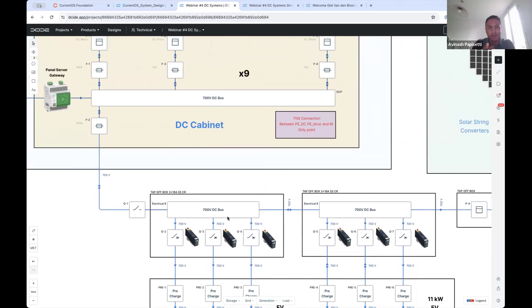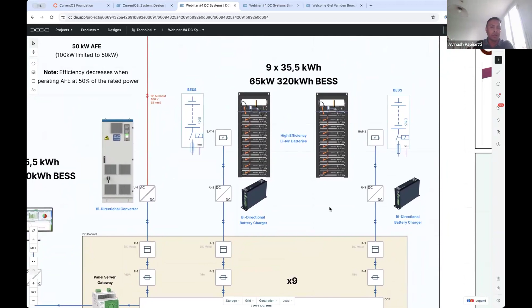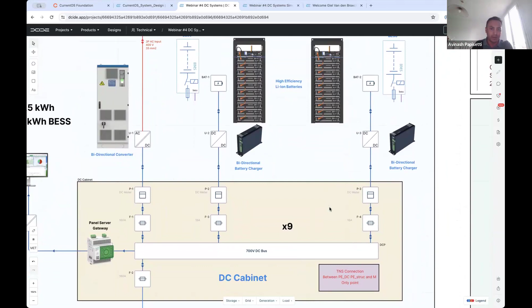On the DC bus, I have coupled multiple energy storage cabinets, each approximately 35.5 kilowatt hour with around 9 kilowatt of power delivery. I have strung 9 of them together, meaning each energy storage cabinet acts independently. How they act, and on what philosophy, is something I'm going to discuss.